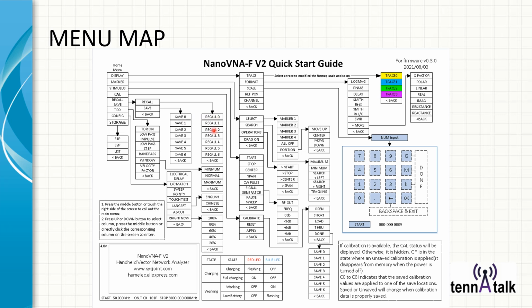But if in doubt, and we'll see how to sanity check if you've got a good calibration, you can do a recall and a quick sanity check, and if it checks out, you're fine, you don't have to recalibrate. That's given that you're in the frequency range that that particular storage slot was set for, and it'll generally tell you what frequency range it was calibrated to. So once I'm calibrated, I look at the frequency subrange of interest. Like if I was looking at 20 meters, my antenna might not be resonant in the 20-meter band at all. So if I've scanned from 3 to 30, I should be able to find it, hopefully, somewhere in that frequency range. And if I'm either high or low outside the 20-meter band, I'll know it. And then I can make a quick coarse adjustment.